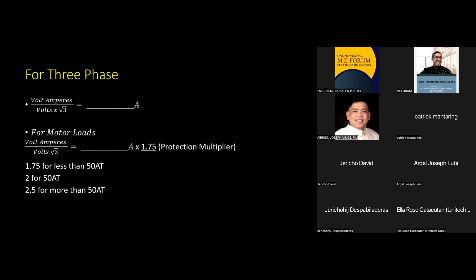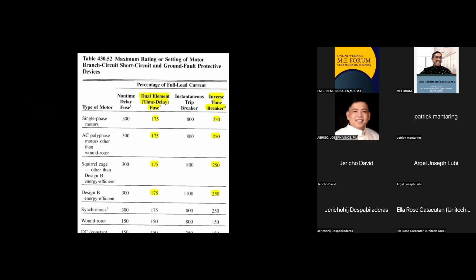Now, it is always square root of 3, it cannot be square root of 2 or square root of 4. It is always square root of 3. By the way, the reason it is square root of 3 is because it is 3-phase. So if you are told you have a 3-phase supply, or the motor you will use is 3-phase, then automatically we have 1.732 in the denominator in solving for current.